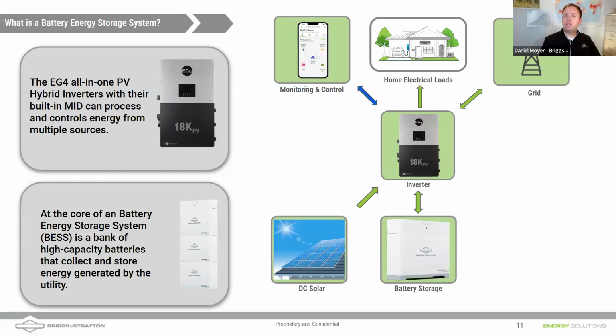Of course, in a lot of situations, we are going to bring in DC coupled solar through the charge controllers to charge up those batteries during the day, and discharge the batteries to the home loads at night. That's especially useful when we're in a state or a utility that doesn't allow net metering, which is becoming more and more common. We used to have net metering, the ability to use the grid as our battery.